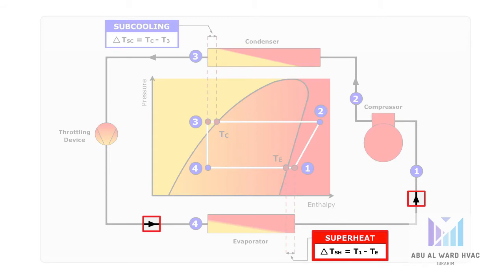In front of the compressor, the simplest way of doing this is to use a fixed throttling device such as a capillary tube. This is typically done in, for example, household refrigerators and in other simple systems where optimization is not the selling point. A fixed throttling device can, however, only be effective for one set of operating conditions. This is where the TXV has a huge advantage.